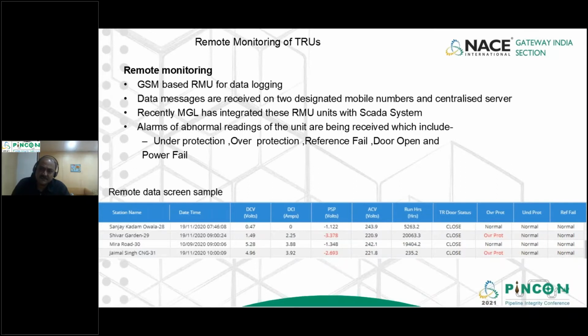The SCADA system is of ABB, and all the RMUs, all the CNG stations are on SCADA units, all the sectionalizing valves are SCADA units, the regulating stations are with the SCADA, and the remote monitoring units are also integrated with the SCADA system. Now, the alarms are under protection, over protection, reference fail, door open, and power fail.